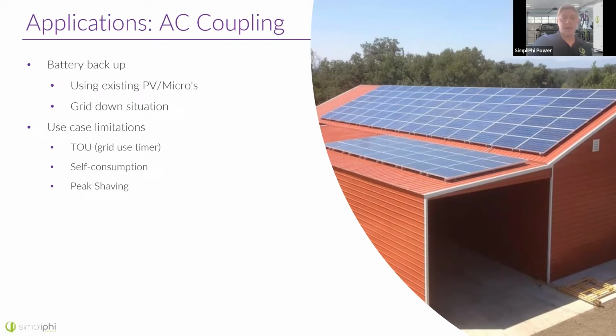However, keep in mind, if you're grid tied, then that grid down situation, when it occurs, you need to be prepared for that frequency shifting to occur. You've got to make sure that's built into your system. Otherwise, when the grid goes down, your PV array will not be producing power. So if your battery-based inverter cannot produce a grid signal or frequency shift, then you will not be able to produce power when the grid goes down. And this is something that I think a lot of simply grid-tied PV customers don't realize. They buy a PV system and don't realize that their power is not going to stay on during an outage. And the fact is that if you don't have batteries, that is not a distributed asset. That's a distributed generation source. But you don't have control over that power until you add batteries and a battery-based inverter.